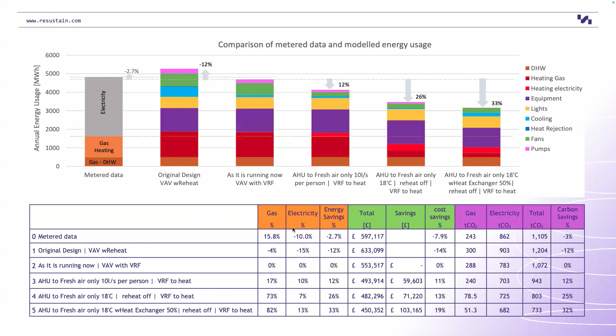So what we did, we started optimizing. We put the fans on an occupancy schedule, and we put the supply air temperature at a steady temperature, not at 28 degrees. I would just like to add, here you can see what happens. This is the calibrated model prior to optimization. And this is, I think, the calibrated model after optimization.